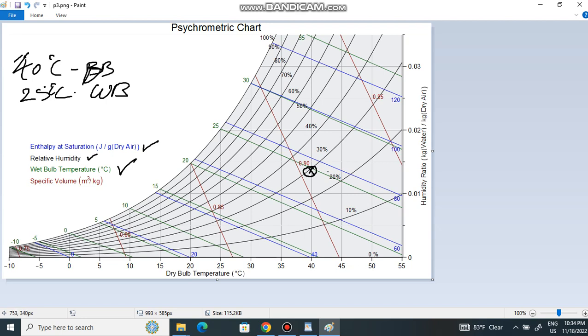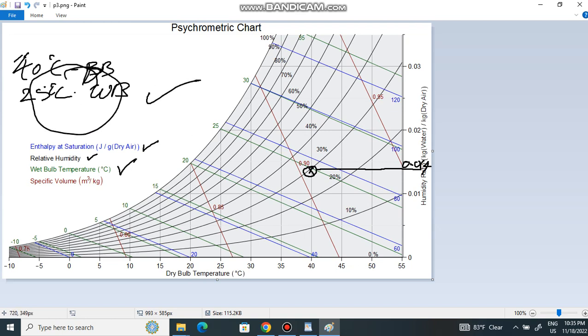From that intersection point, if I draw a perpendicular horizontal line to the Y-axis, I can read the humidity ratio — it falls between 0.01 and 0.02, approximately 0.014. This means this condition of air has 0.014 kg of water per kg of air. Also, reading the relative humidity curves, this point is near to 30% RH, meaning the air is 30% wet and 70% dry — it can still absorb more moisture.